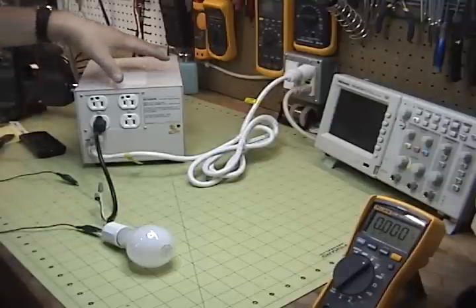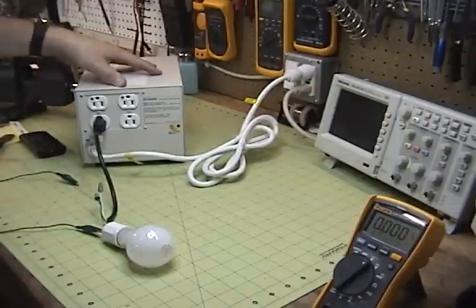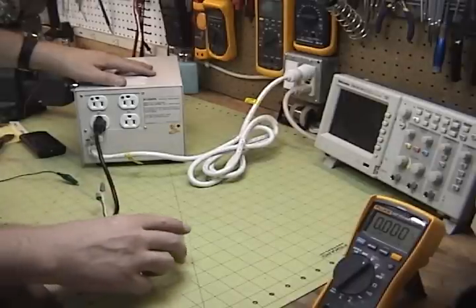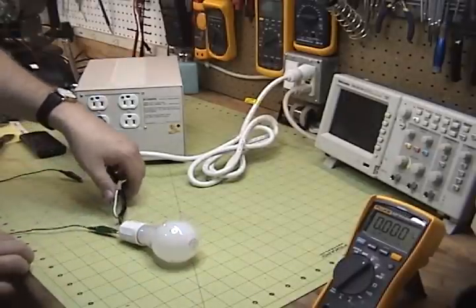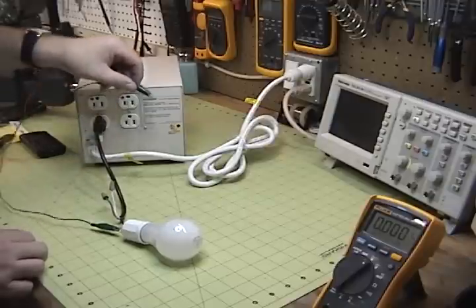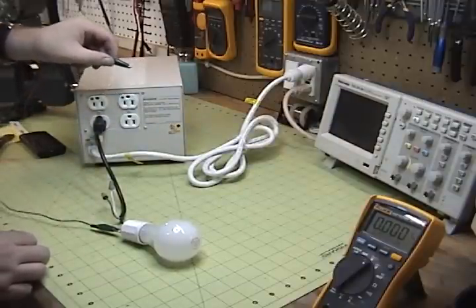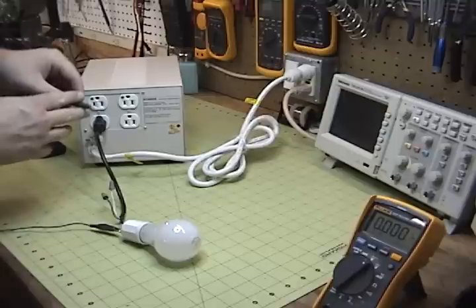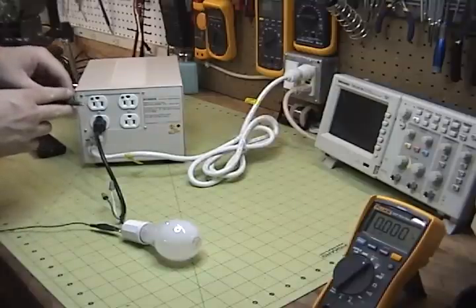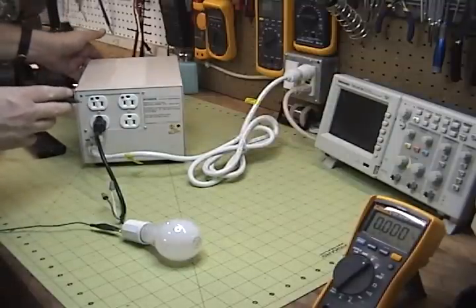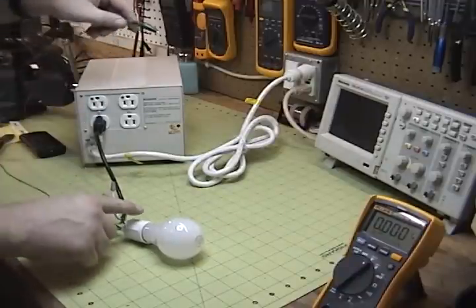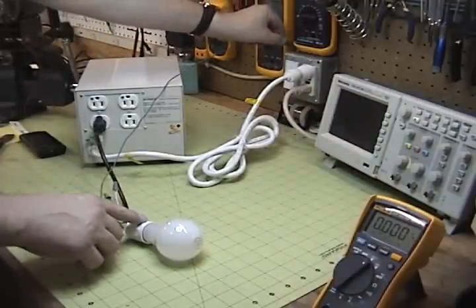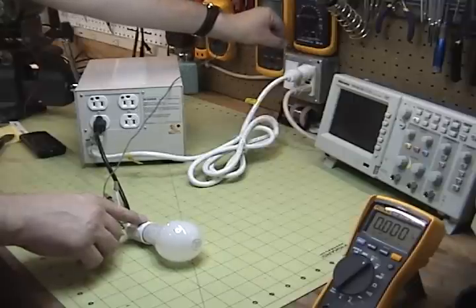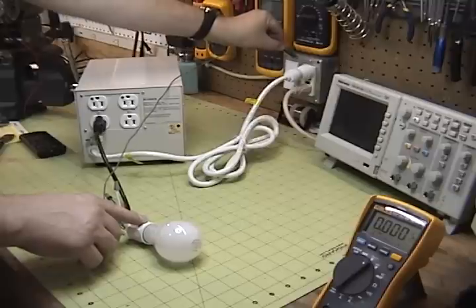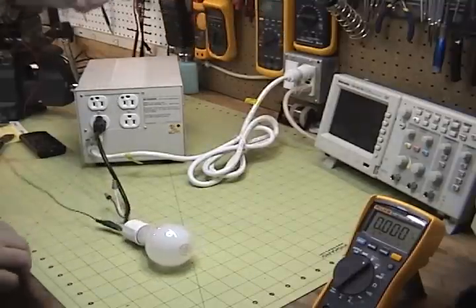Our transformer's back together - it's now a tech version of an isolation transformer. We have our light bulb hooked up again with just that single leg hooked up. The other leg is hooked up to this alligator clip. We're going to show that we no longer have that dangerous potential voltage with current to ground anymore. So we'll turn the transformer on. I'll reach over here and touch the grounding, essentially at any point that's ground - this is essentially the ground point of my house - and nothing, the light bulb isn't lit. And that's good, right?